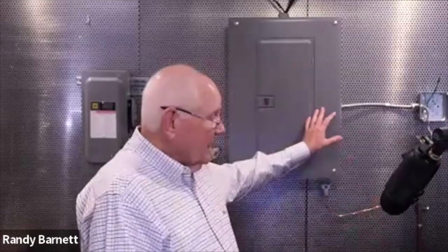When using cable ties, do not over tighten. We talk about cable ties in the NEC, but it doesn't say anything about if you over tighten them, you could damage the insulation. Yeah, I guess I knew that, but it's not something that I would normally think about, but something I should pay attention to. All conductors shall be identified in the panel board. So inside the panel board, every wire that comes in there should be identified. Whether I use some type of wire label or a tag or whatever it is, it lets me know what that conductor is supplying, probably what breaker it's going to and so forth.